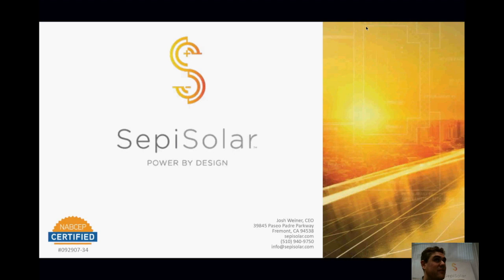This is actually a point of study at SepiSolar. We're trying to understand things like round-trip efficiency. A lot of folks quote efficiency at the cell level, not the system level, or they only include the coulombic efficiency of the battery itself, not all the series and parallel connections between packs, not to mention the HVAC, thermal management, and auxiliary loads. All of that factors into round-trip efficiency, and those numbers change over time — air conditioners get less efficient over time. So round-trip efficiency is not a constant; it's a nuanced characteristic to dig into.